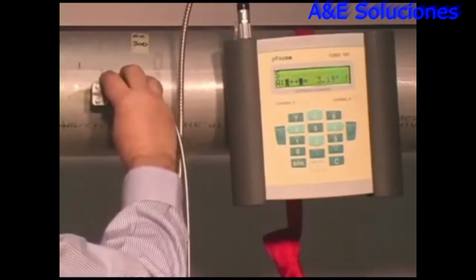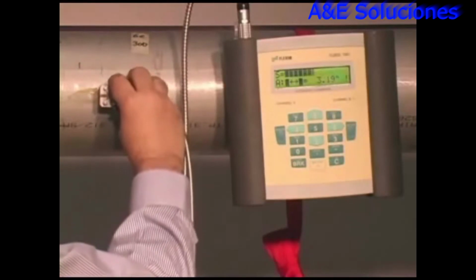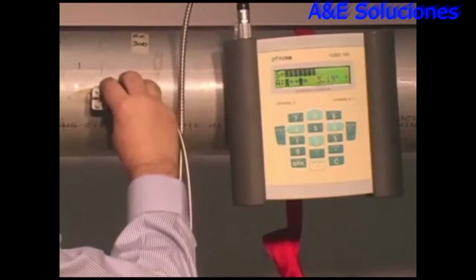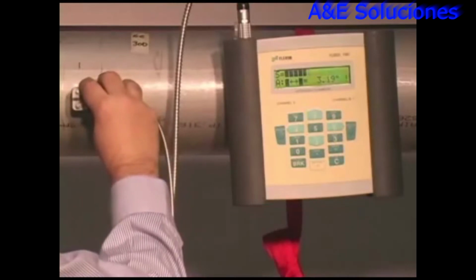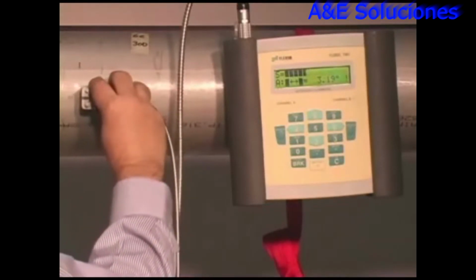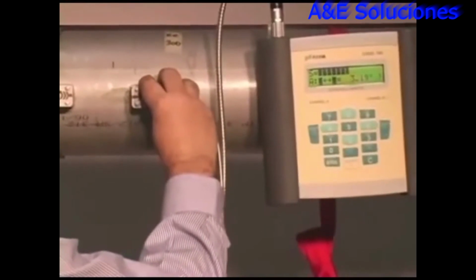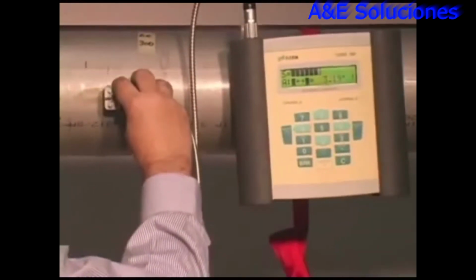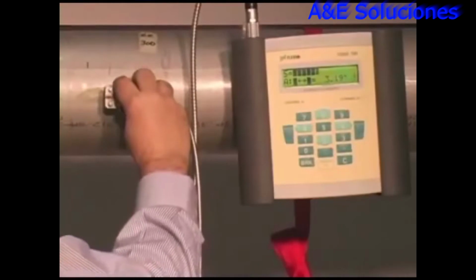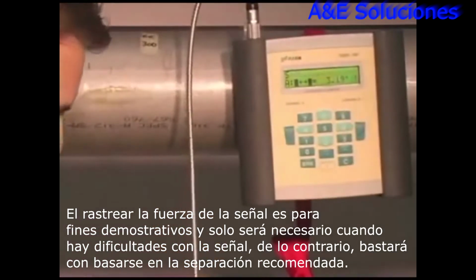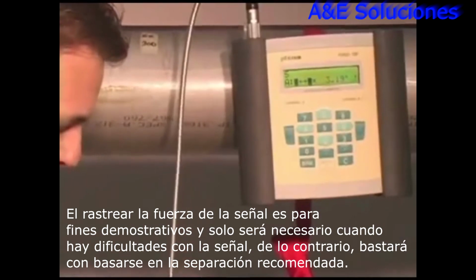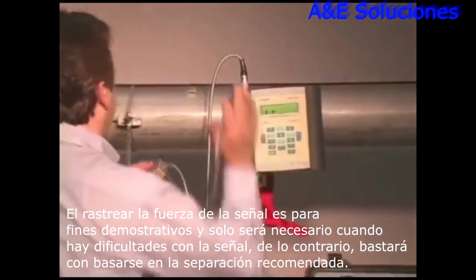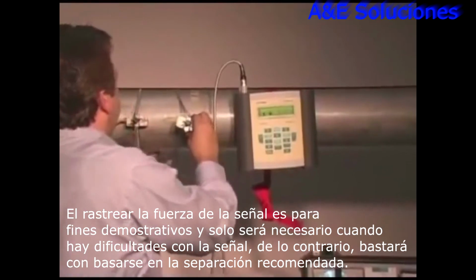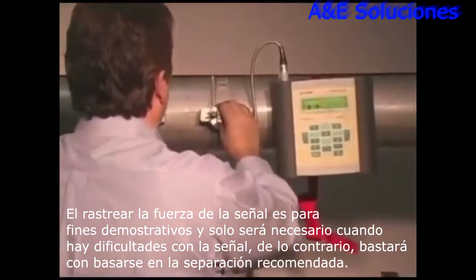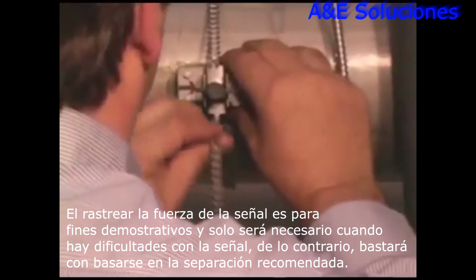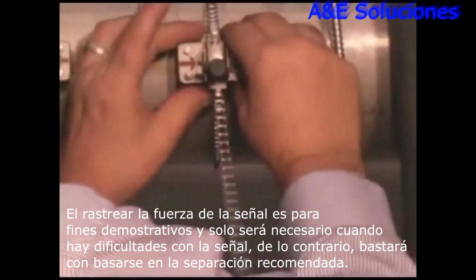Okay, I'm going to show you this one more time. I'm just holding one transducer on the pipe, and as I slide it in closer, you see the signal dropping down. Now I'm sliding out, and you see the signal increasing, and this is closer to the 3-inch point. Now we don't necessarily want to slide the transducer back and forth when we install the meter. I'm just giving you a demonstration here. What we want to do is measure it out and put it at the recommended spacing. We would only engage in that type of optimization if we had a weak signal.